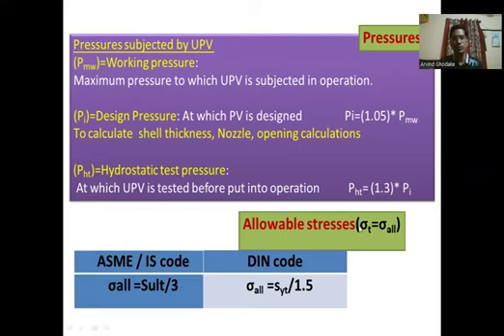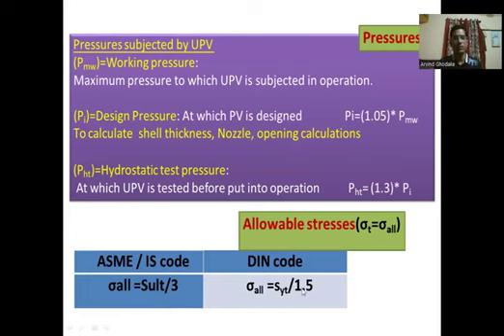The allowable stress should be equal to the tangential, hoop, or circumferential stress. As per ASME or IS code, sigma allowable = SUT / 3, where SUT is the ultimate tensile stress. According to DIN code, sigma allowable = SYT / 1.5, where SYT is the yield tensile strength.